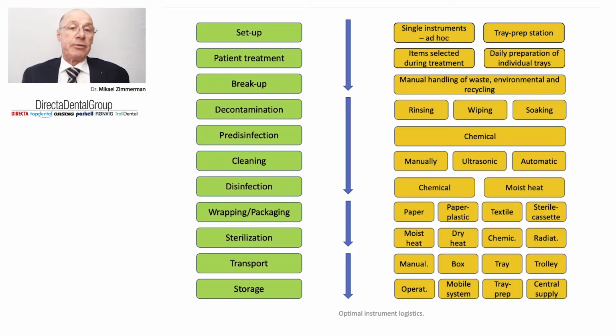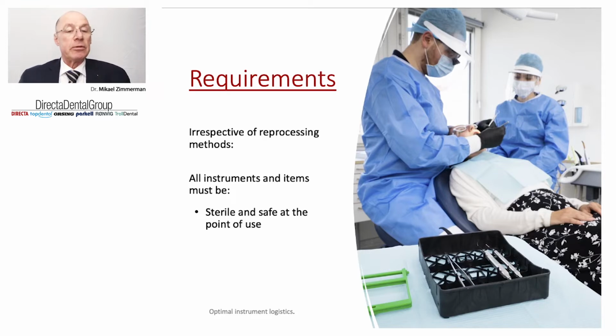There are, of course, a lot of different methods how you can reprocess your instruments. Looking at this slide, on the left side you have all the steps necessary when reprocessing your instruments, and on the right side, the orange boxes, you see examples of all the different methods that could be used. Irrespective of what type of reprocessing method is being used at the clinic, the final requirement must always be that all instruments and items must be sterile at the point of use. Without giving any value to whether certain methods are better or not, the end result must always be the same, and can always be the same if you carry out all the different procedures in the right manner.